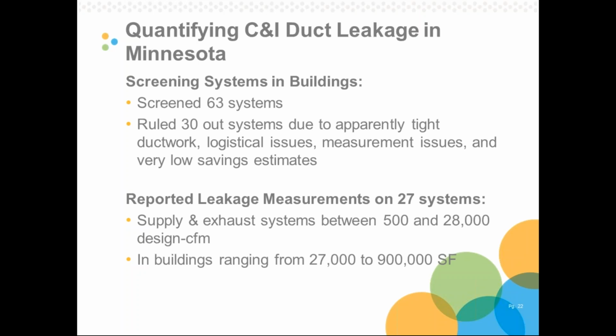And we ended up with a pretty large range of systems. This let us hope to understand how leakage might correlate with all sorts of building and duct system characteristics. We ended up testing supply and exhaust systems between 500 and 28,000 CFM in buildings ranging from 27,000 to 900,000 square feet. The buildings were generally office space, education, classroom space, clinical space, childcare, a lot of the types of end uses you see in commercial institutional buildings.